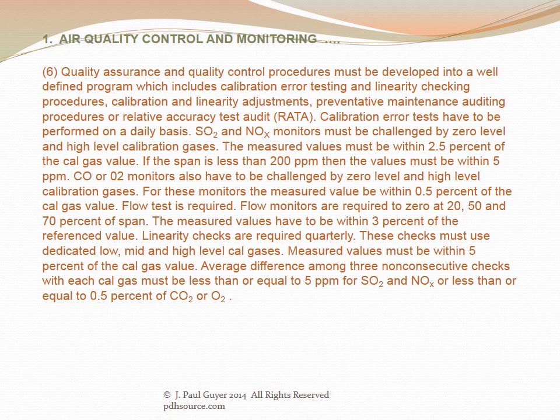Quality assurance and quality control procedures must be developed into a well-defined program, which includes calibration error testing and linearity checking procedures, calibration and linearity adjustments, preventative maintenance auditing procedures, or relative accuracy test audit, abbreviated RATA. Calibration error tests have to be performed on a daily basis. SO2 and NOx monitors must be challenged by zero level and high level calibration gases. The measured values must be within 2.5 percent of the cal gas value. If the span is less than 200 parts per million, the values must be within 5 ppm.